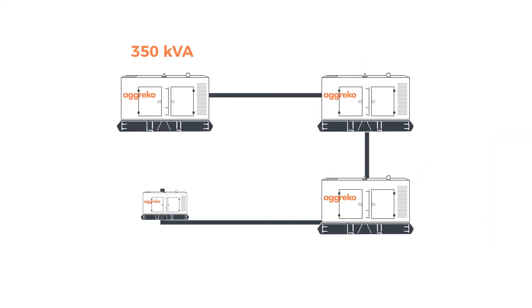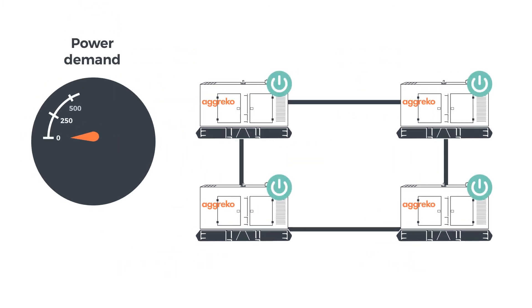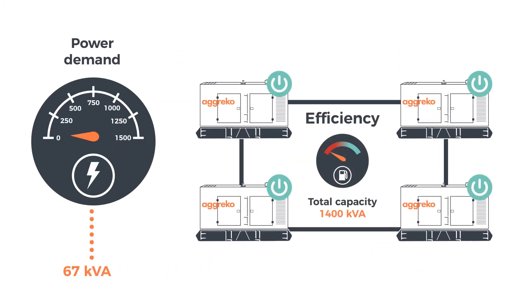Using Aggreko's Load On Demand solution, you can have four 350 kVA generators providing a total of 1400 kVA — plenty for peak demand. Current demand is a steady 250 kVA, so three of the generators automatically shut down. When more power is required, the next generator automatically starts to meet demand.